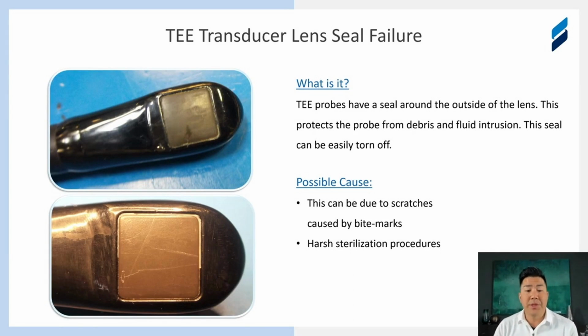So continuing on with the TEE probe, this is a better pictorial representation of the seal being degraded. You can see on one side here on this probe, but as you trace around the edge, you can see the corrosion that's occurred, and then the RTV just comes off. It loses its adhesive properties. It's acidic no matter where it's living. When it's getting decontaminated, it's in acidic and caustic fluid. When it's inside the esophagus, there's all that stomach acid, and so you can see that circling down here, the RTV starts to degrade and break down over time.